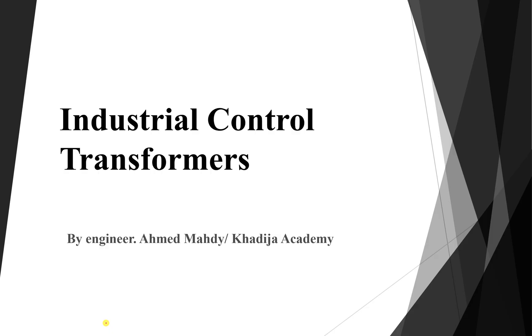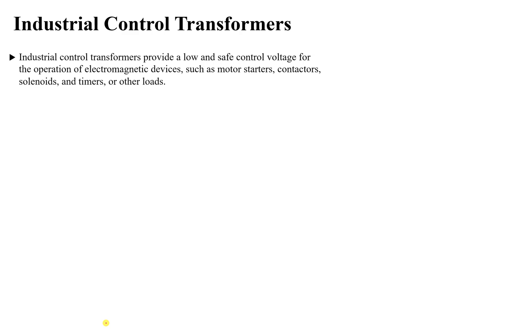Let's talk about another type of transformer called the industrial control transformer, or in another way they are called motor control transformers. These transformers are used in control circuits of motors — for example, they are used to step down the voltage into a low and safe voltage for the operation of electromagnetic devices like motor starters, PLCs, contactors, relays, timers, and so on. They are used in motor control circuits, which use low voltages like 48V, 12V, or 110V, depending on the device.